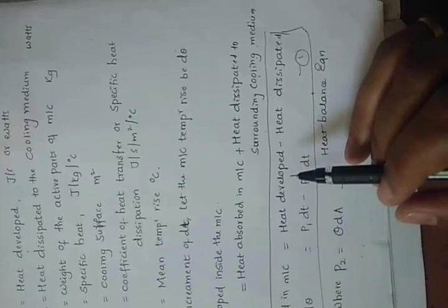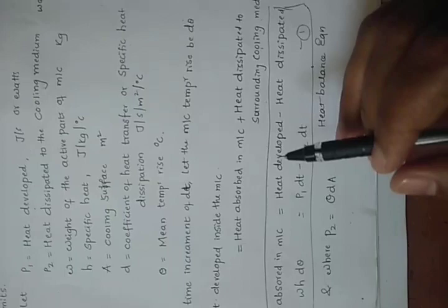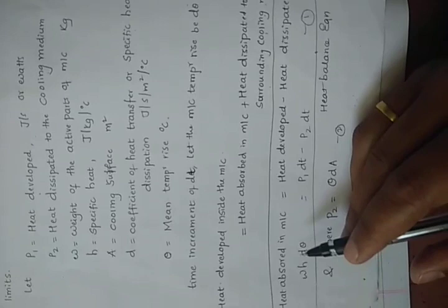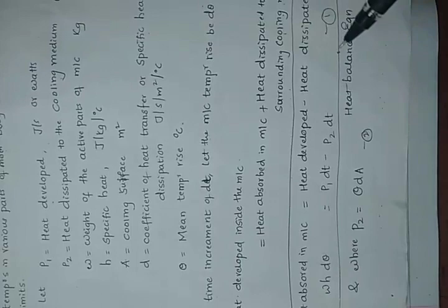Heat absorbed in the machine is equal to heat developed minus heat dissipated. Same equation, we are just rearranging. That can be written as WH d theta equals P1 dt minus P2 dt. This is called the heat balance equation. Using these parameters, we are making the heat balance equation.